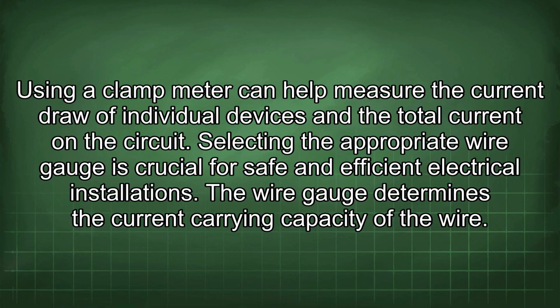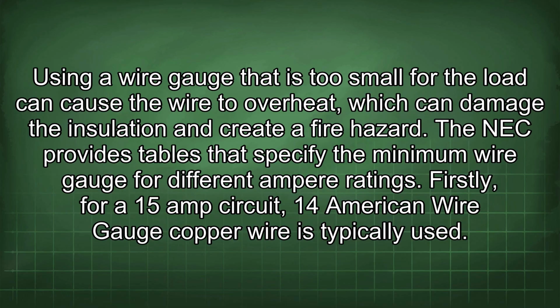Selecting the appropriate wire gauge is crucial for safe and efficient electrical installations. The wire gauge determines the current carrying capacity of the wire. Using a wire gauge that is too small for the load can cause the wire to overheat, which can damage the insulation and create a fire hazard.